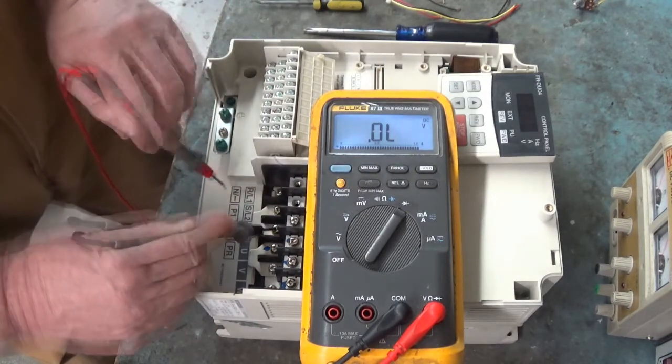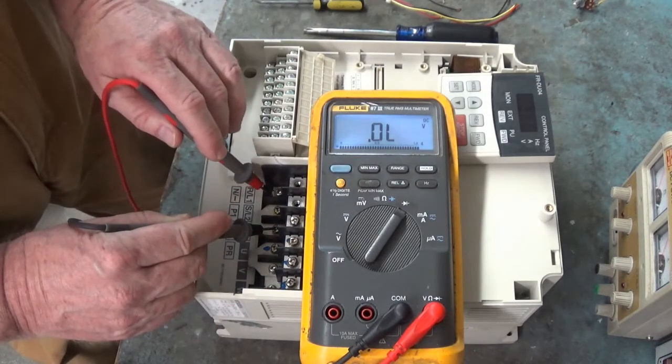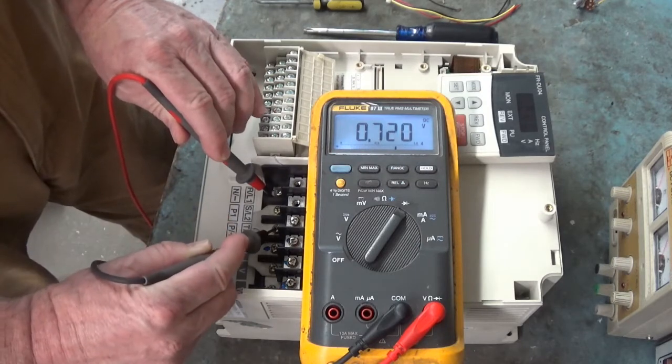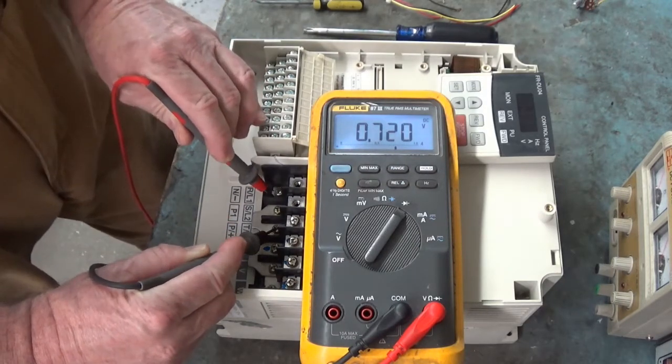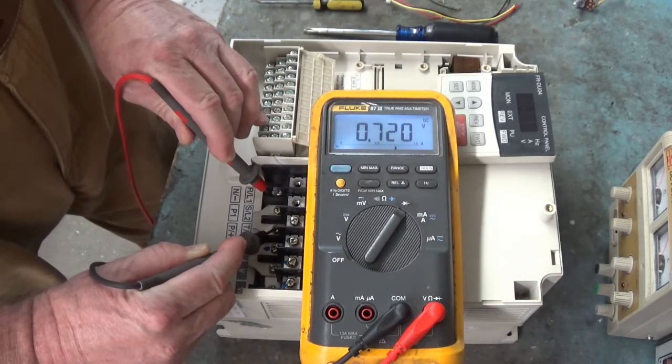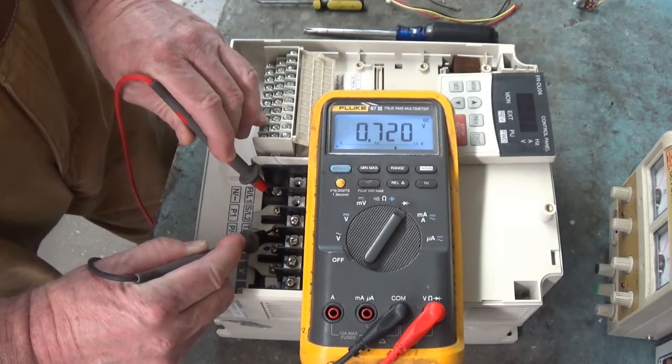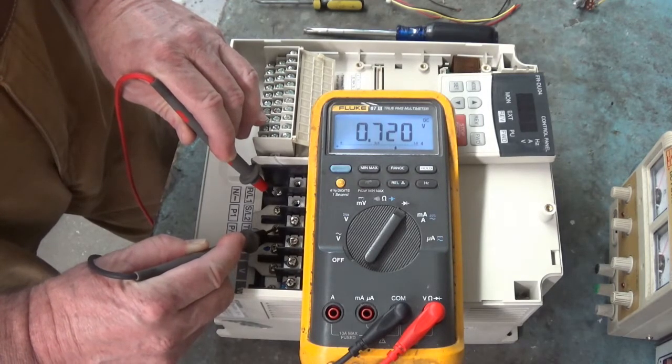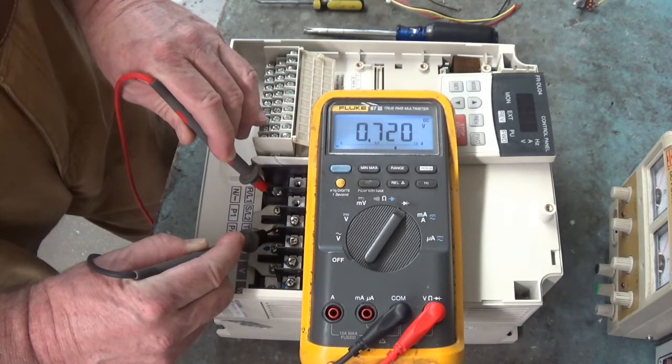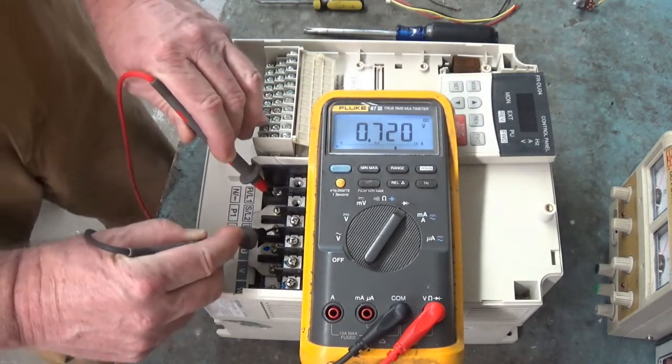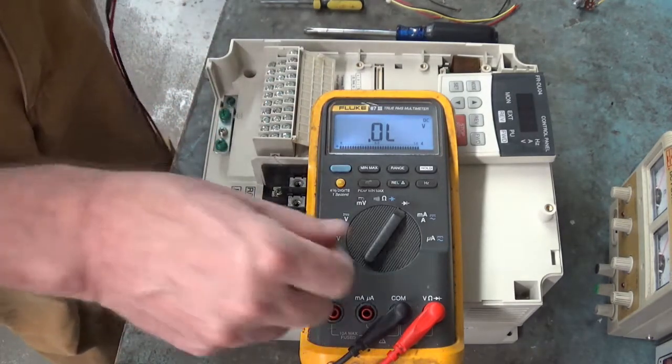Let's put the red lead on N slash minus and leaving the black lead on P slash plus. There's the diode drop for the bus. That's good. 0.720. All right. No short circuits.